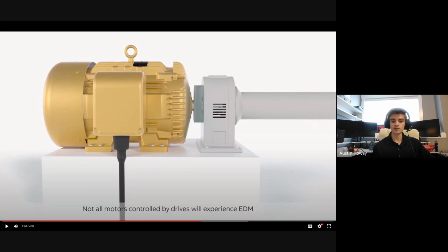And the other thing to note is on the bottom it says not all motors controlled by drives will experience EDM for this scenario. The reason for that is because, like I said, there are certain variables that you can put in place. There's certain grounding brushes, but there are different trade-offs, and that's what it's going to get into, the different solutions, how older solutions provide a somewhat solution, but they're not the best choice. And that's what we're going to weave in and out of, what the best choices are, what are the more modern choices, and how that's engineered, and the advantages that come with that too.